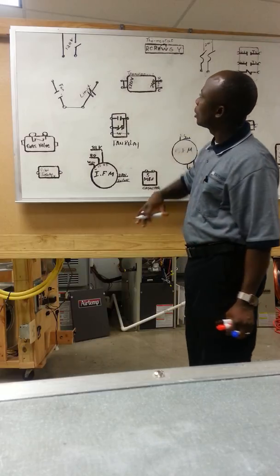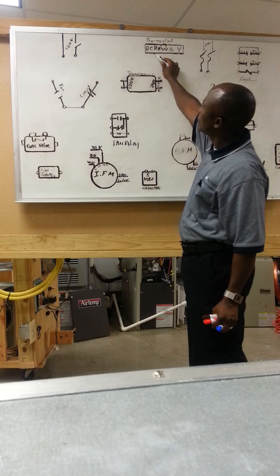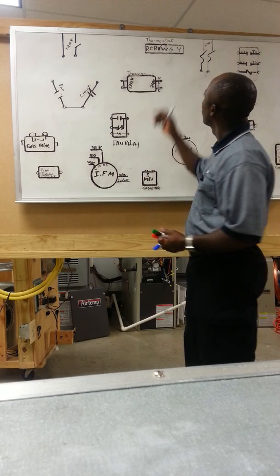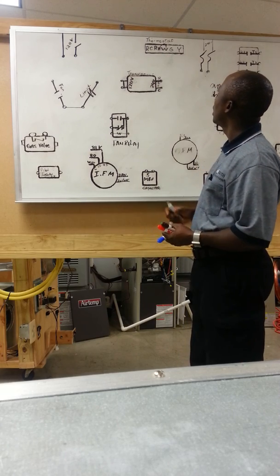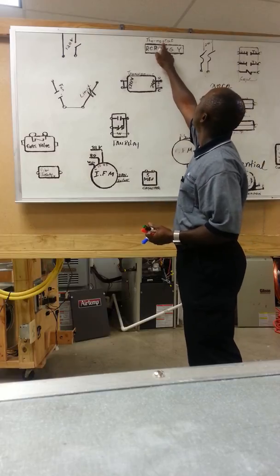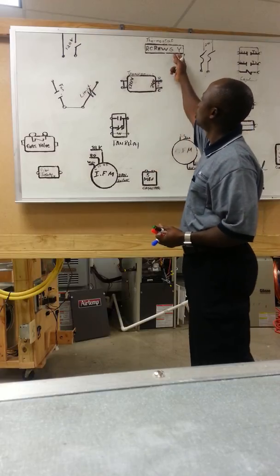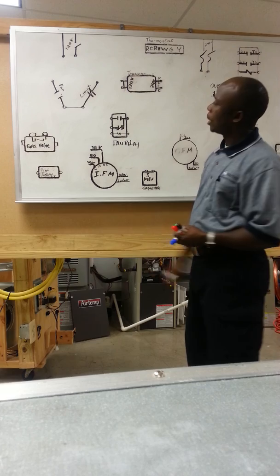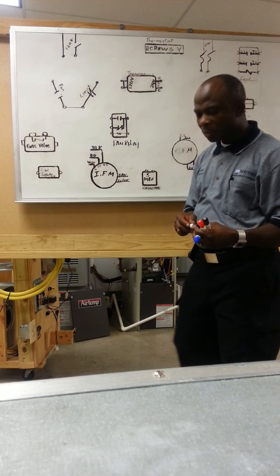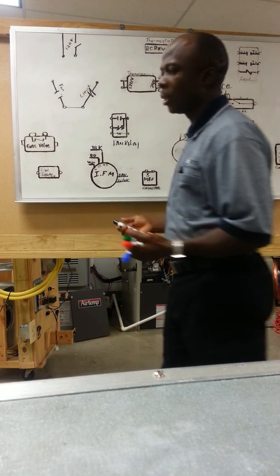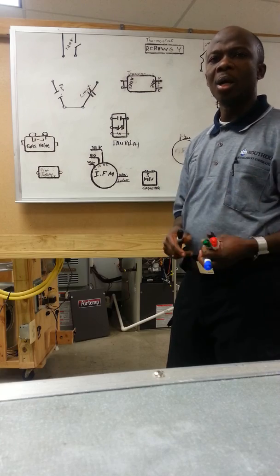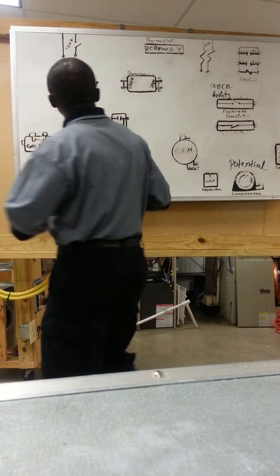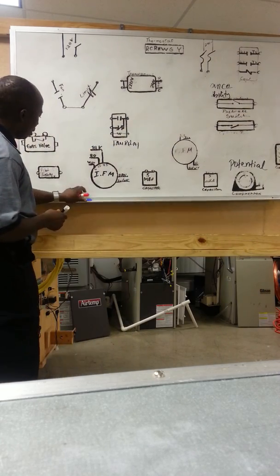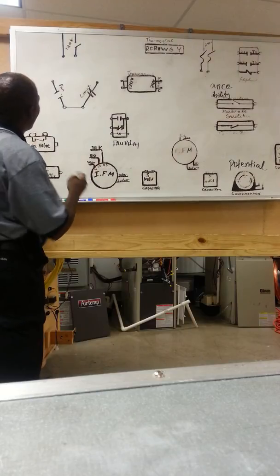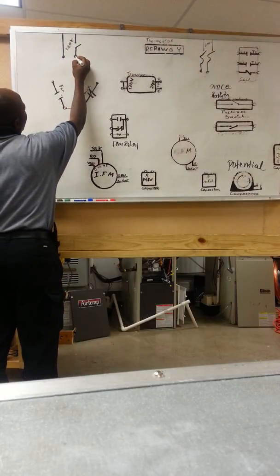And we have our thermostat. We have the RC, which is 24 volt cooling, and RH, which is 24 volt heating. The W is for heating, G is for fan relay, and Y is for the cooling contactor. So now let's wire this component, and then we can talk about in detail how the components work. So coming from here, we're going to get our main power, 120 volts.